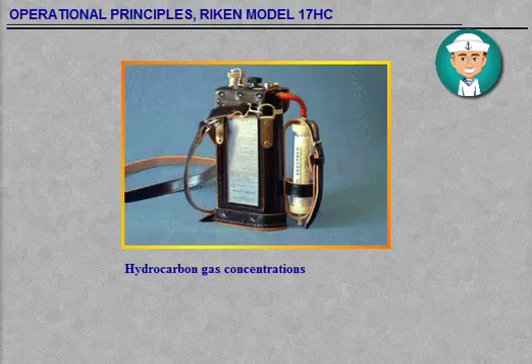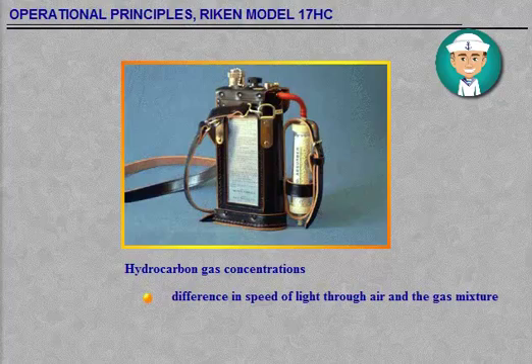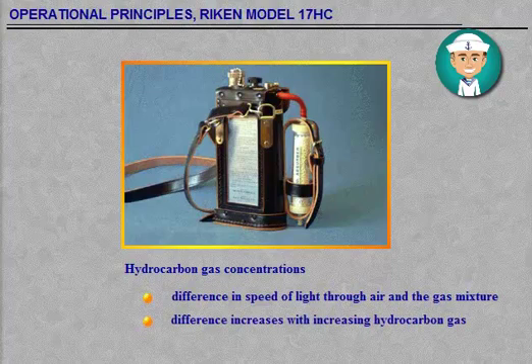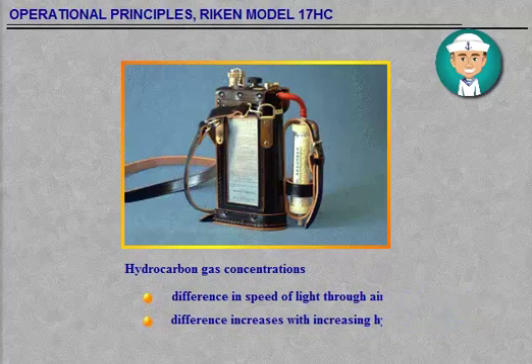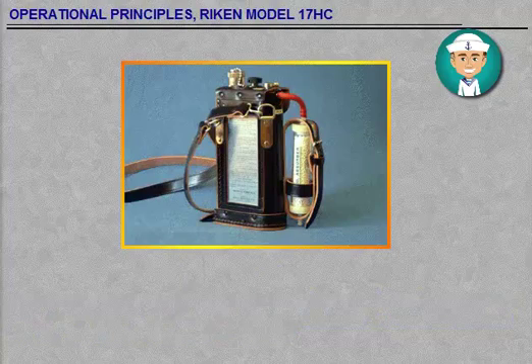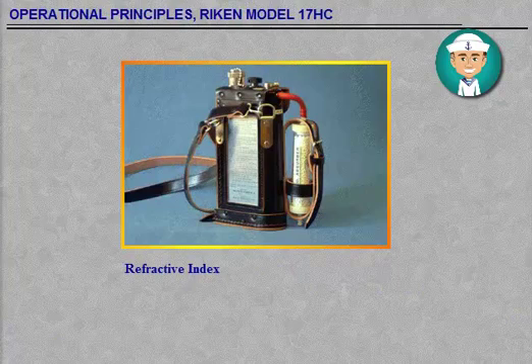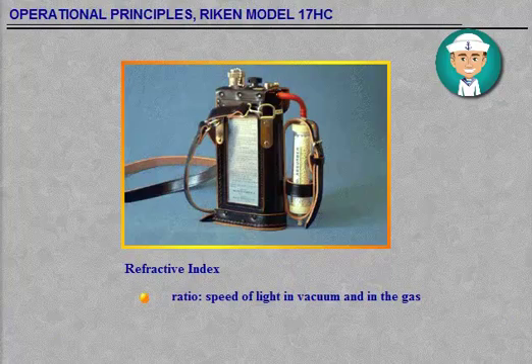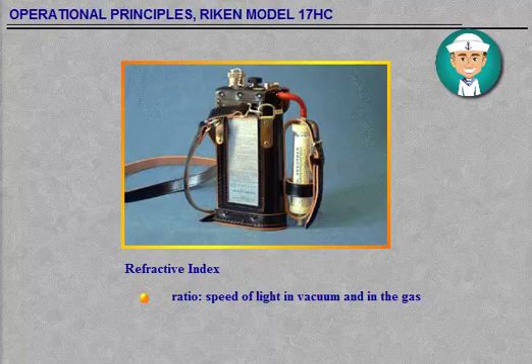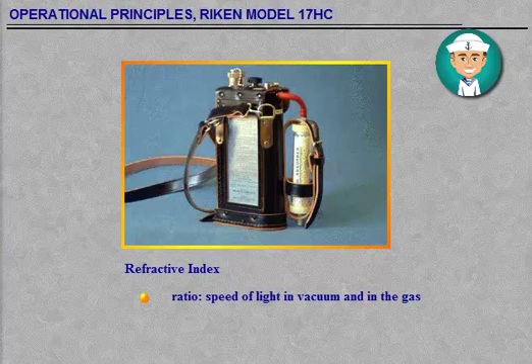With the RIKEN 17HC, concentrations of hydrocarbon gases can be measured by utilising the difference in the speed of light through air and through the gas mixture being measured. The difference increases with increasing hydrocarbon gas concentration. The refractive index for a gas is an expression of the ratio between the speed of light in vacuum and in the gas. The speed in the gas will depend on pressure and temperature, and the refractive index is normally quoted for a pressure of one atmosphere and either 0°C or 20°C. Compared with the refractive index for the various hydrocarbon gases, the index of the hydrocarbon mixture used by RIKEN is closest to butane.